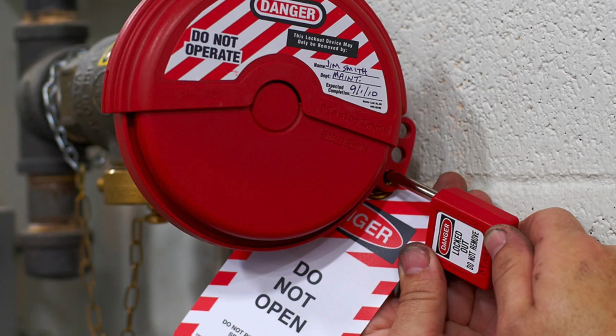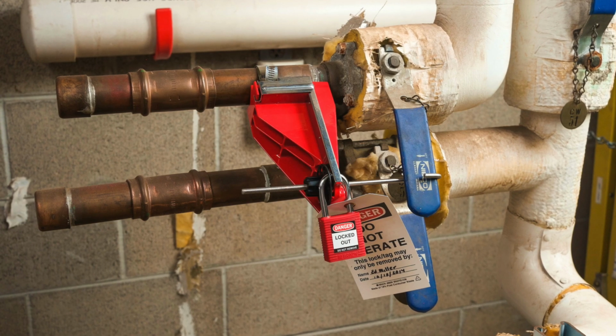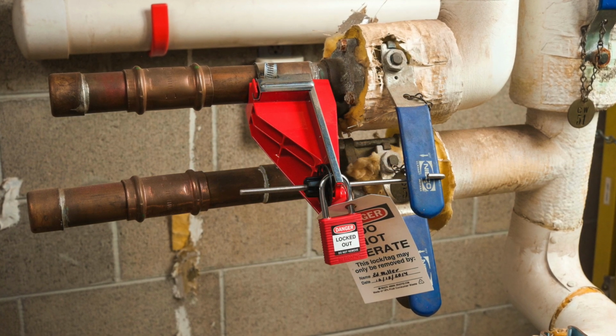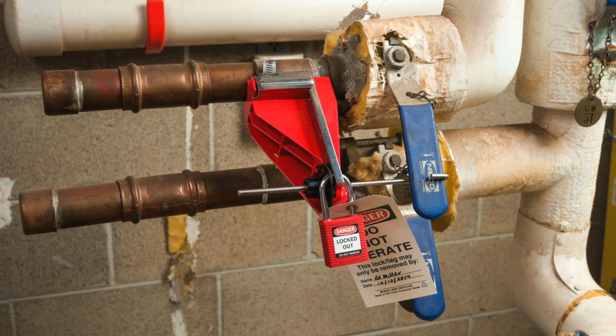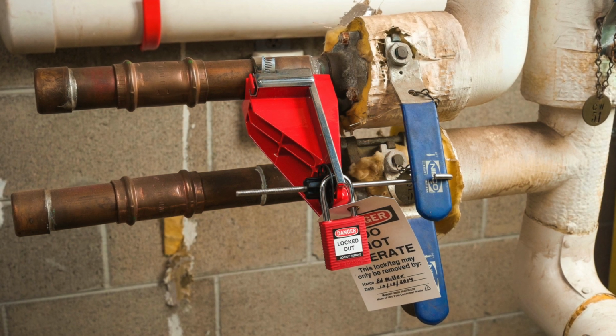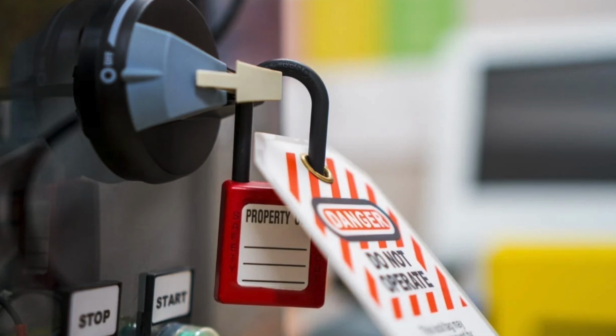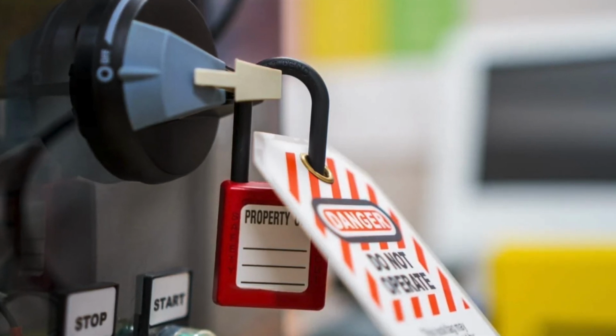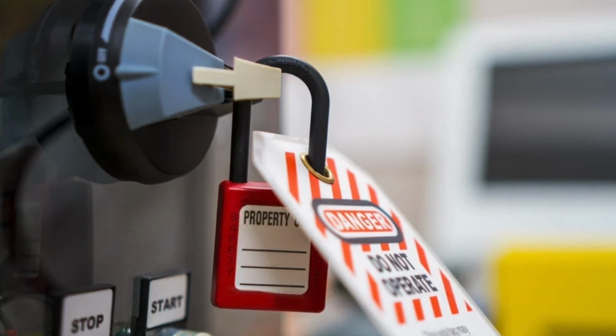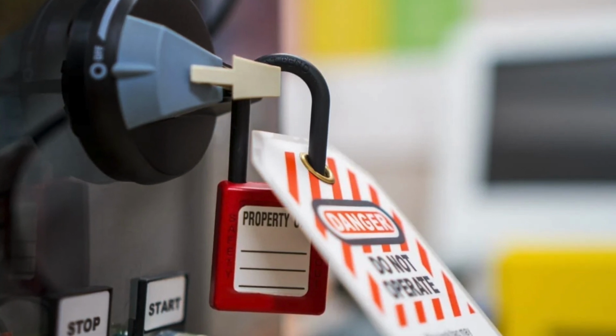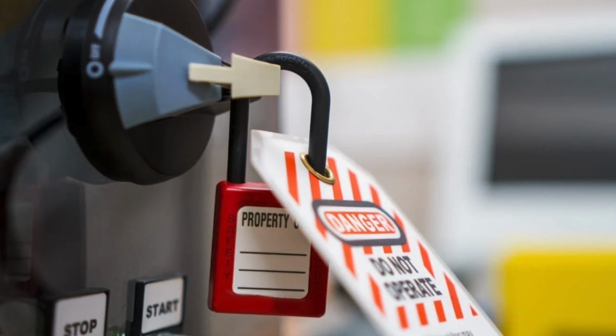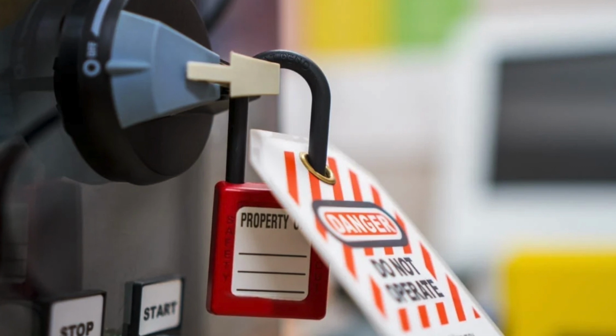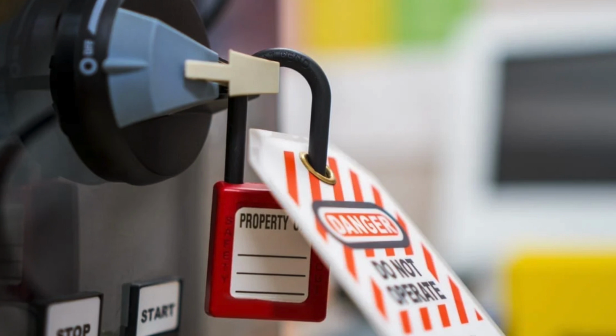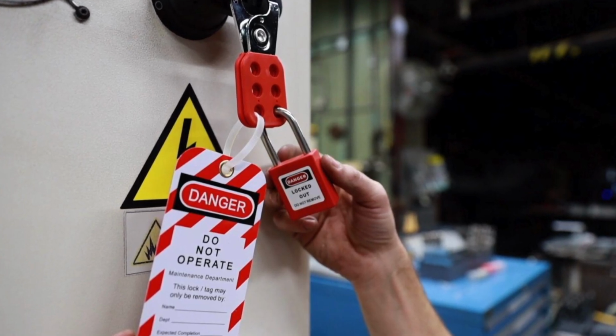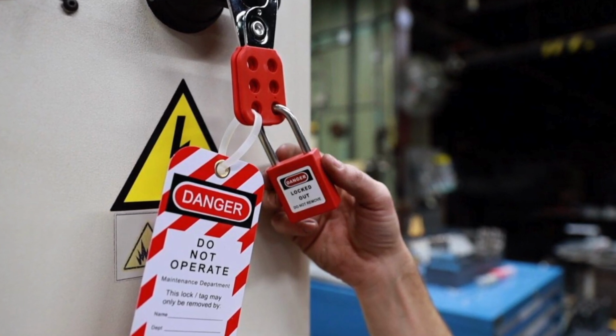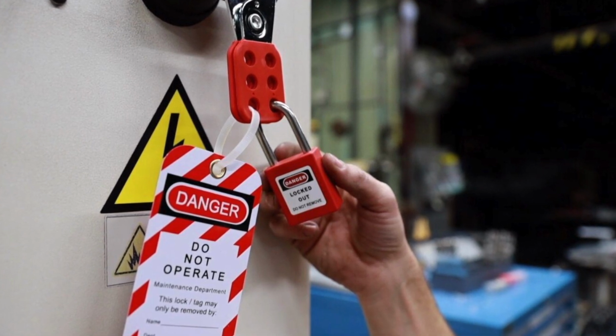When a piece of equipment needs to be locked out, you can proceed with locking out and tagging the machine's energy sources. You should use the lockout tagout mechanisms that are designed for the energy isolation devices, such as electrical panel circuit breakers and valves, that you are working with. Some facilities store all lockout tagout equipment in a central location, and there may be lockout tagout logs in which authorized employees must sign the devices in and out.